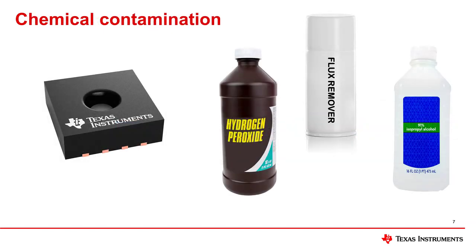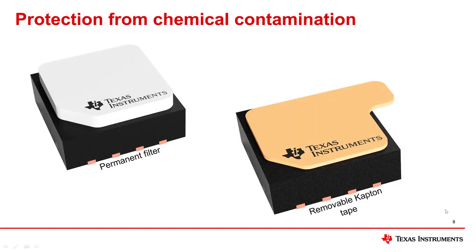Many humidity sensors are in open cavity packages where the sensing polymer is exposed directly to the ambient air. As a result, humidity sensors should not be exposed to volatile chemicals, such as solvents or other organic compounds. Exposure to certain chemicals can cause the humidity output readings to drift, which may be irreversible. The opening in the package allows the sensor to sense the relative humidity in the air, but also exposes the polymer to the environment, making it sensitive to pollutants.